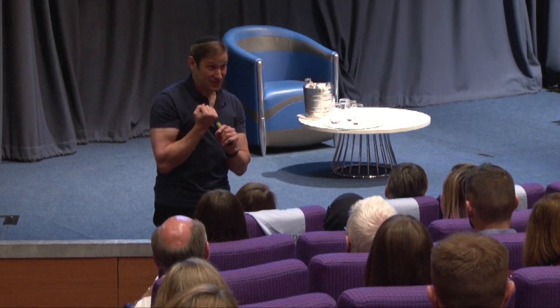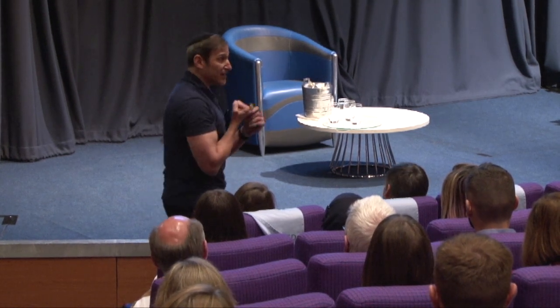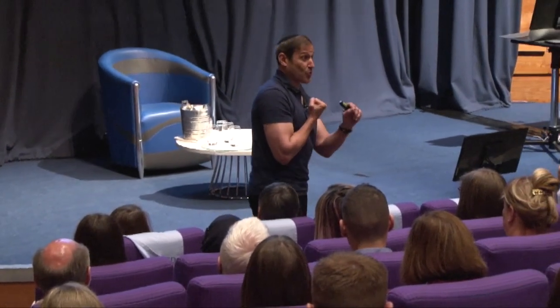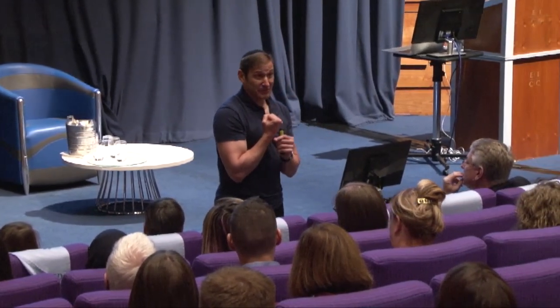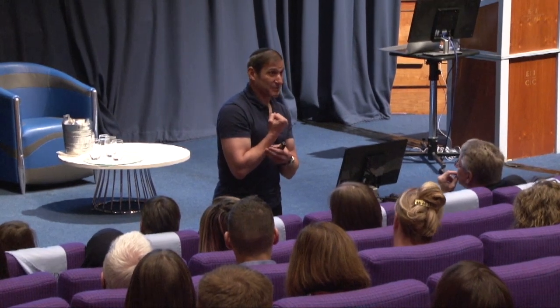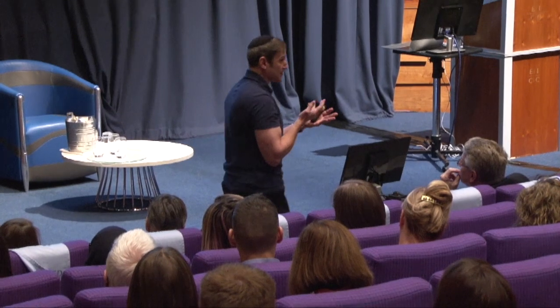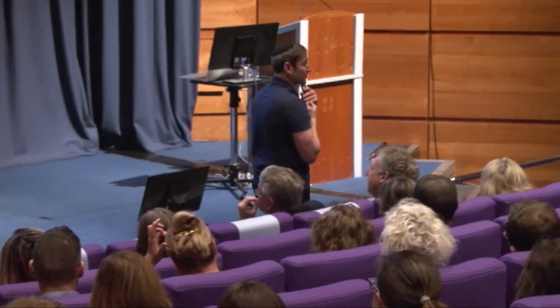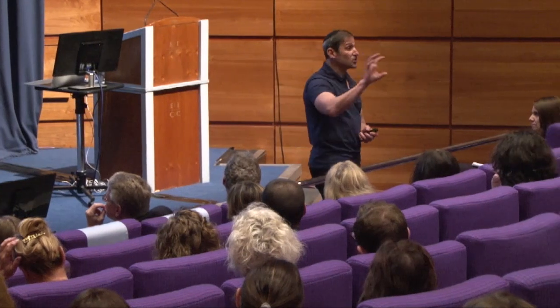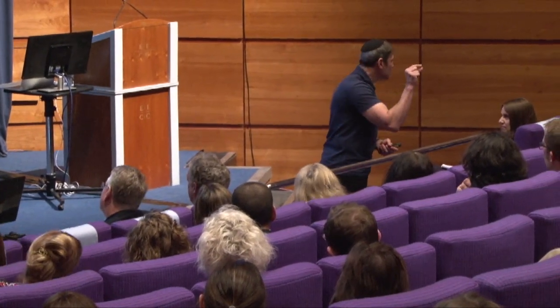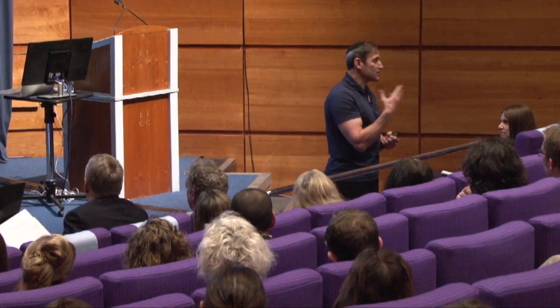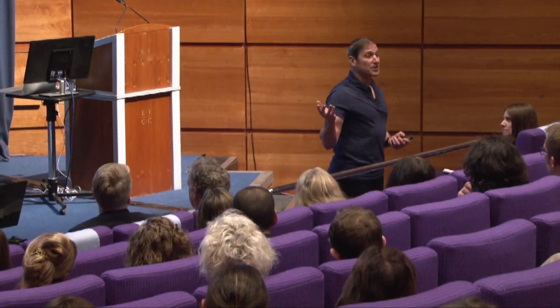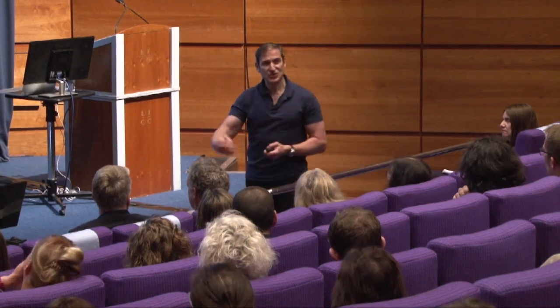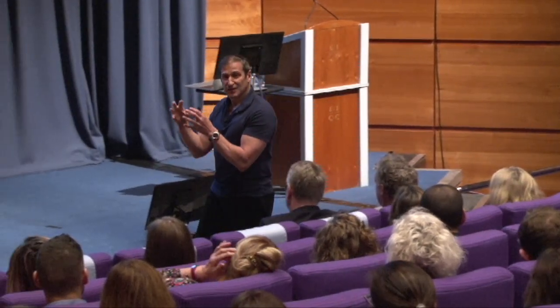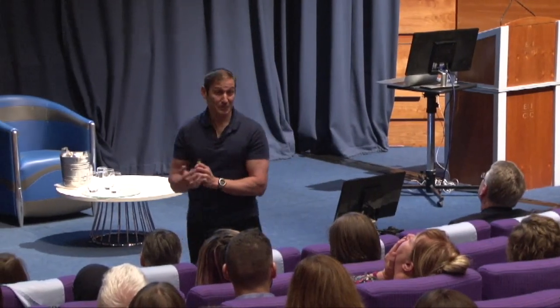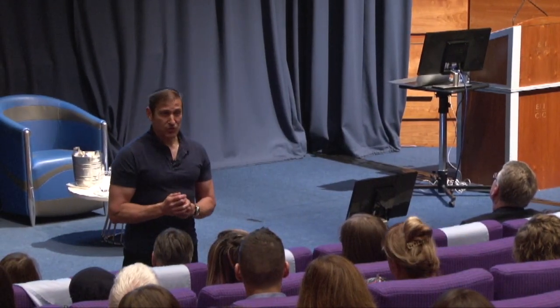It still says 6—just like my last car said 120 miles per hour, but it wasn't going to do 120. You understand? It says 6, but there's zero flow in this position. Yet it says conditionally safe. There's a tiny ferromagnetic spring in the regulator that under certain conditions compresses, and next thing you know you have no flow, even though you think it's doing everything you expect. That's what I mean by the safety of a device the patient may be dependent on during or after MR exposure. Got it?